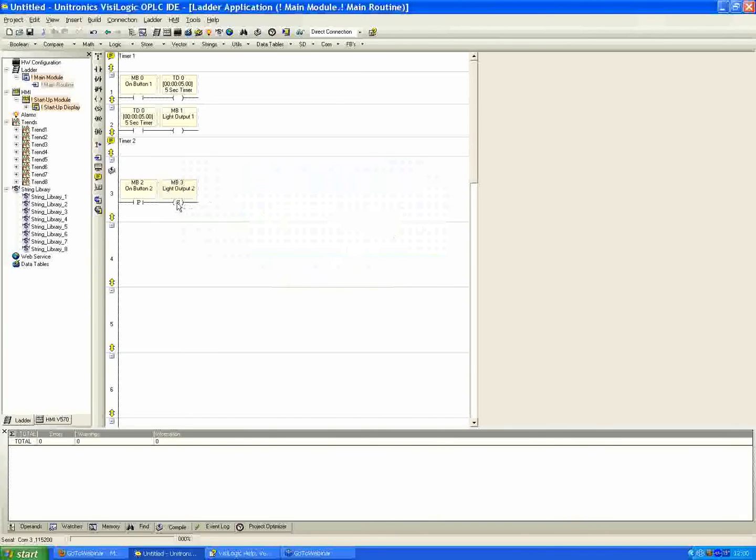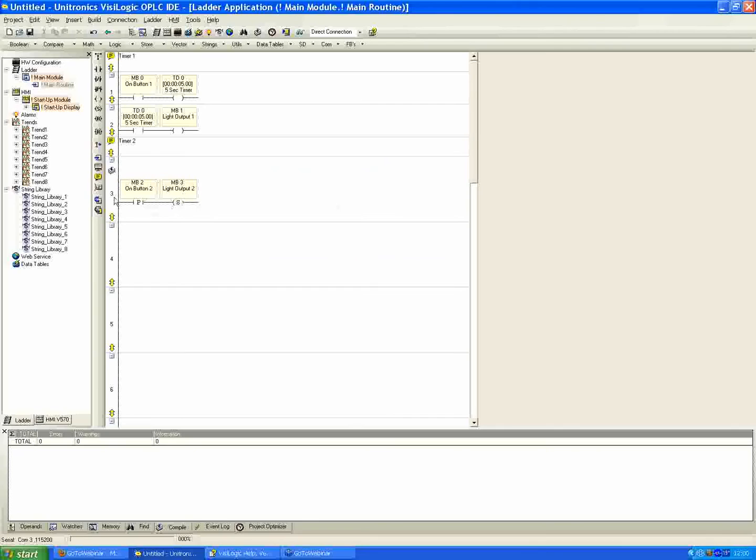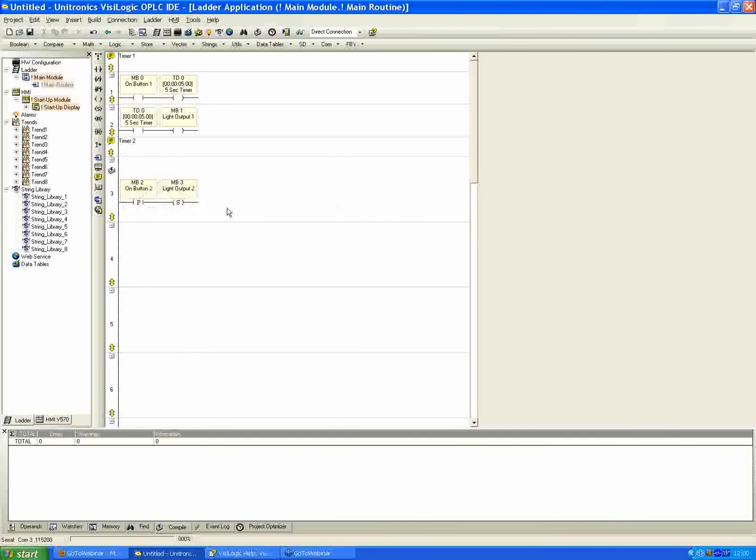And we're going to link this here to our light output 2 or MB3. So let me talk about set coils real quick. There used to be you had to use a latching circuit if you wanted to have a type of hold, a hold action. But we do have set and reset coils in VisiLogic here, which they only require a single shot condition, a single scan. For example, positive transition button press to enable the set coil. So the set or the reset coils only need to be pulsed for a single scan, and then they will hold their state until they're manually changed.